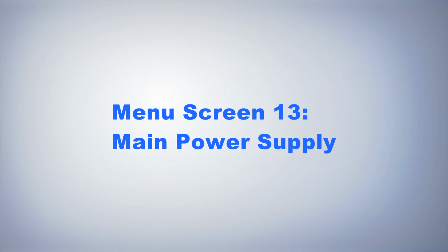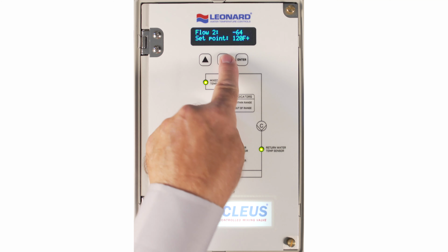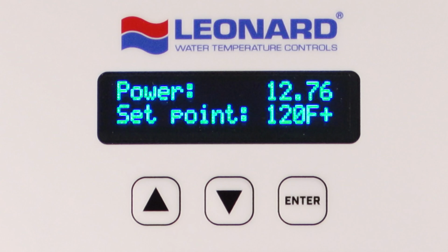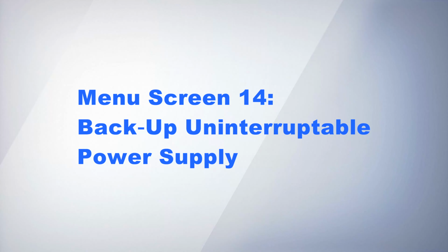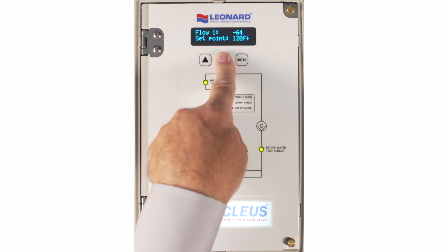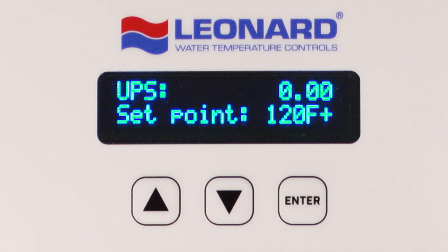Menu screen 13. Main power supply. Pressing down 13 times displays power. This indicates the input supply voltage to the main control board, volts DC, and should always be at least 12 volts DC. Menu screen 14. Backup uninterruptible power supply. Pressing down 14 times displays UPS. If the Nucleus is equipped with an uninterruptible power supply for standby operation in the event of power loss, and there is a loss of primary power to the device, there will be a numerical value in this field, and it should always be at least 12 volts DC.